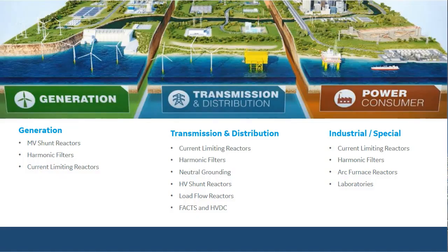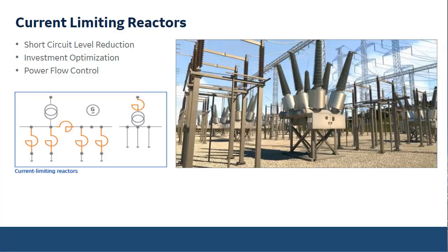There are many applications, and unfortunately, I will not have time to talk about all of them, but this slide is again for reference. You can see that there are many applications from generation to power delivery, but I'm going to focus on the main, most common ones. The first one is a current limiting reactor, or fault current limiting reactor. This is basically an impedance that's added to the system to limit short circuit fault currents.